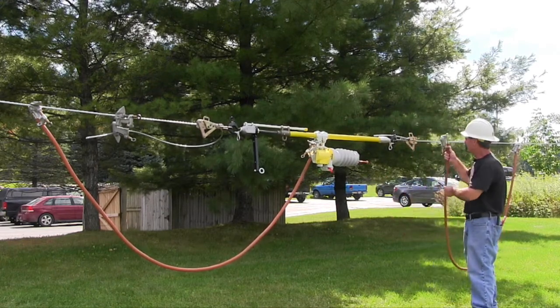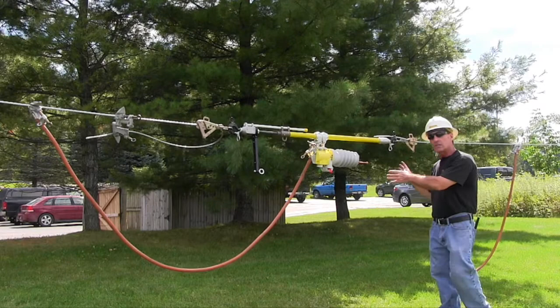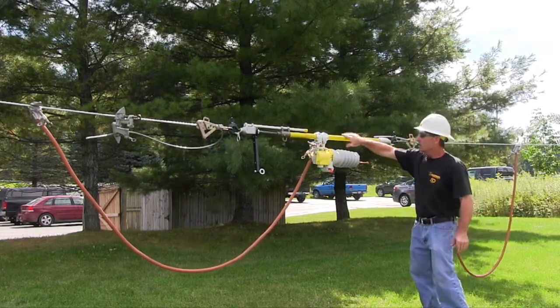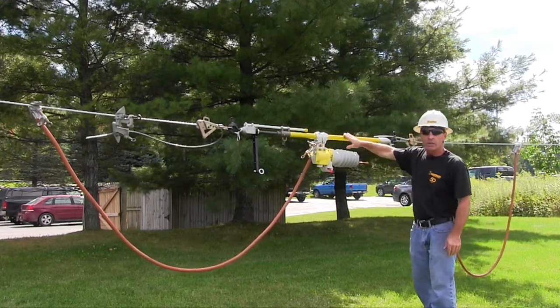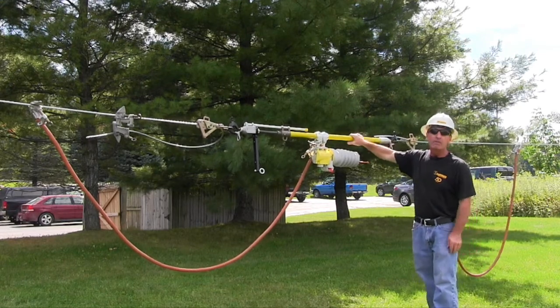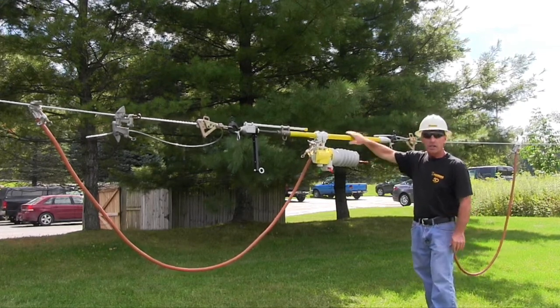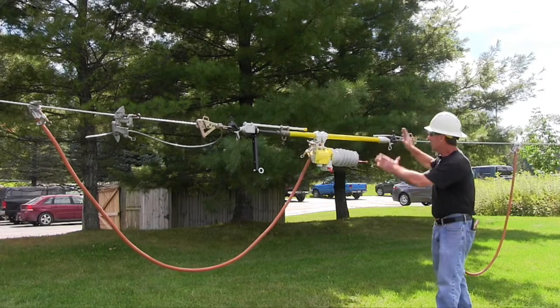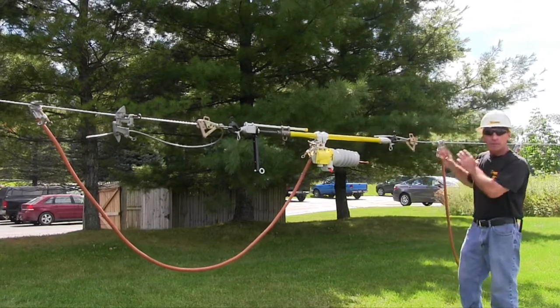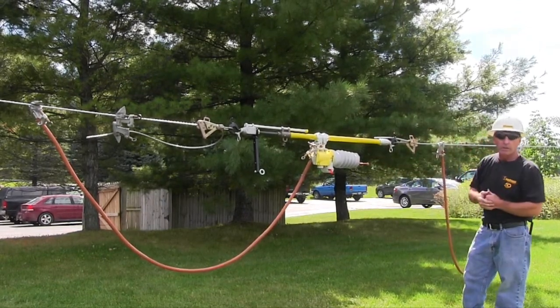Now I can physically see that there's no path. My tensioning tool here is ready for 35kV, so this is insulated up to 35kV. Now I've got a visual open, I can hang my grounds and go to work.